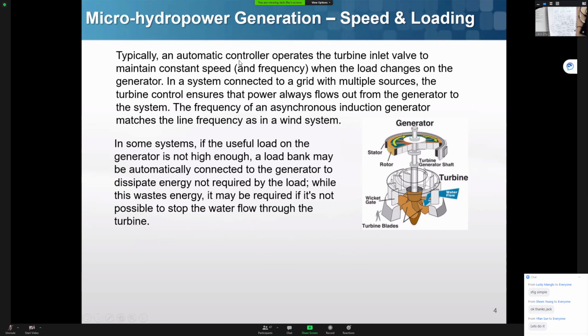So the automatic controls try to maintain the rotating speed. If the load requires more, they will let more water in. More water in, you will be controlling more mechanical power input. But usually those governors are used on a large hydro generator, and for the smaller ones, you might not have those very complex governors.